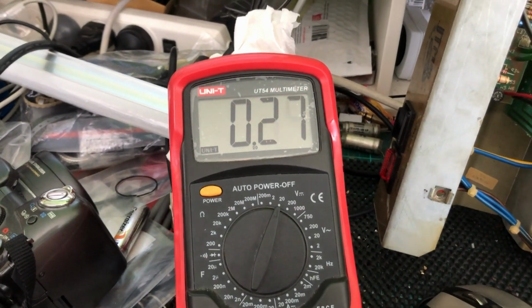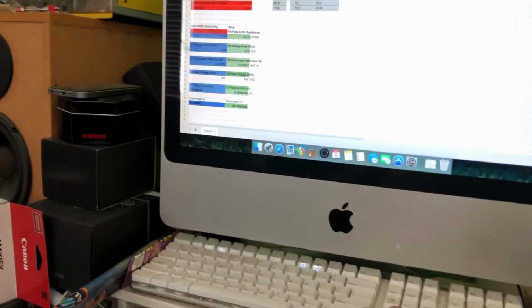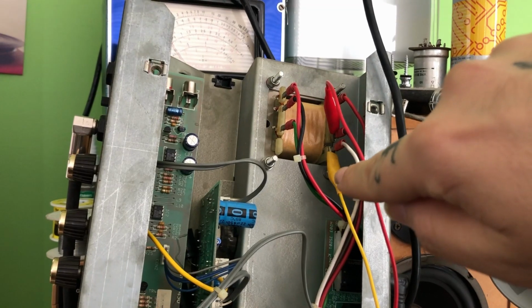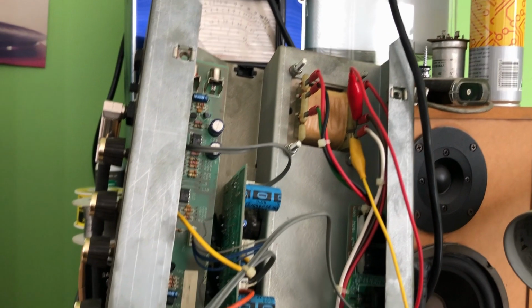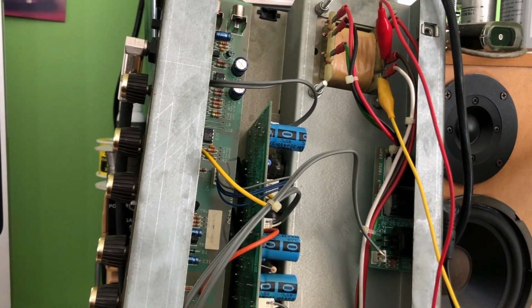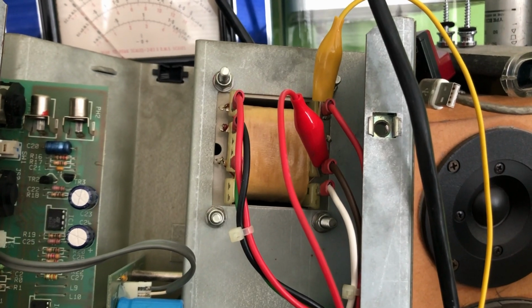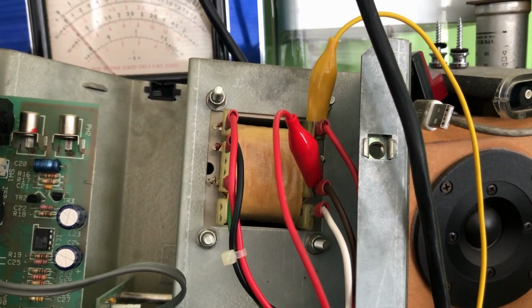3.77 on the white wire. That's what we're going to put in as a voltage drop, 3.77. I'm going to move this yellow cable back to the red cable and we're going to measure the voltage drop on that side. Alright, I've connected the yellow cable to the red cable on the power transformer.